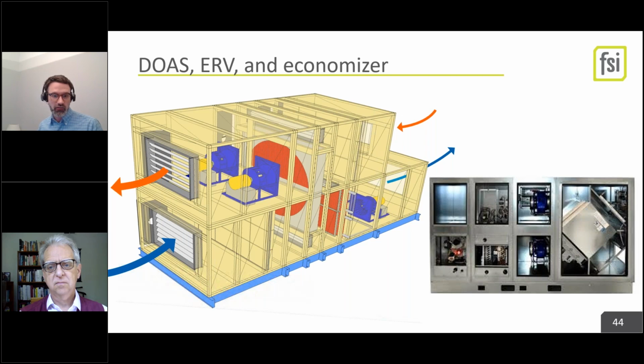Basically, all of your supply airstream can go to outside air so that you get quote unquote free cooling. So if it's 65 degrees outside, but you've got a good solar load, so you definitely need cooling, you can do it with outside air instead of turning on your chiller or your compressor or whatever is doing your cooling. Now, in a DOAS unit, you don't have all of the airstream. You have an indoor unit doing its thing, and then you have an outside airstream. So the economizer only works for the outside airstream.